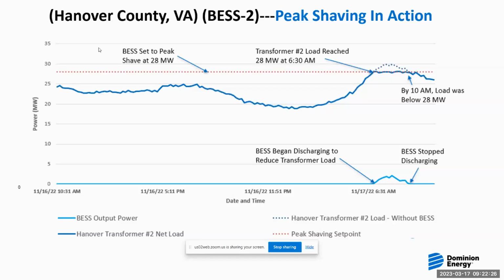That's where battery energy storage comes in—that's really the fascinating thing about what these devices can do. We can park a battery energy storage system just downstream of the transformer, and we can start to discharge the battery right at peak. That's the lower, cyan curve.